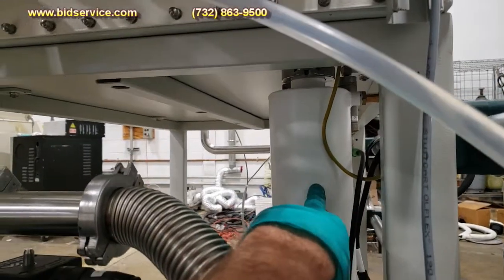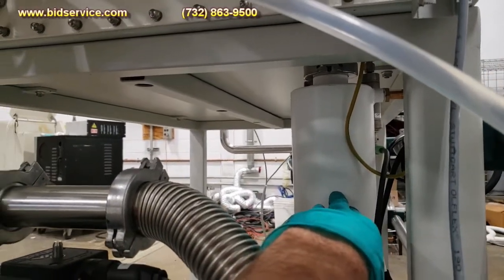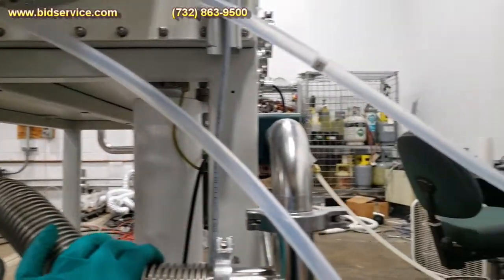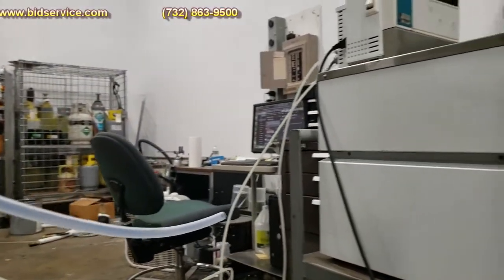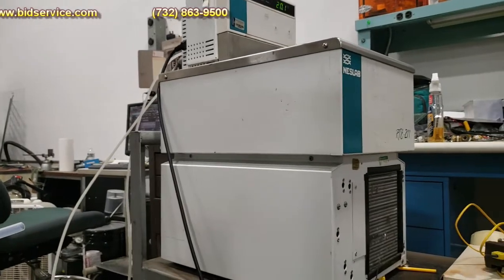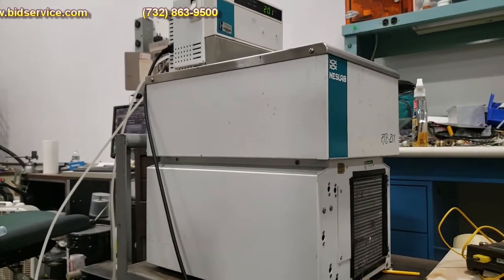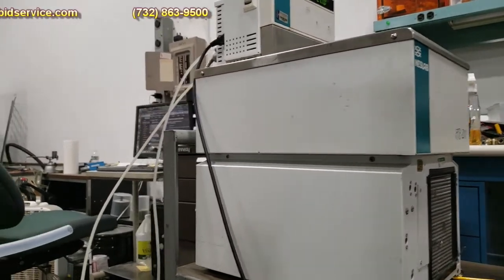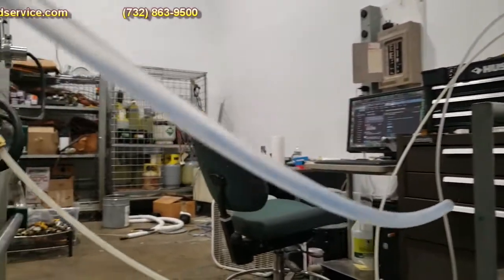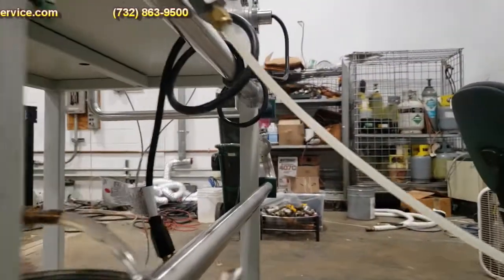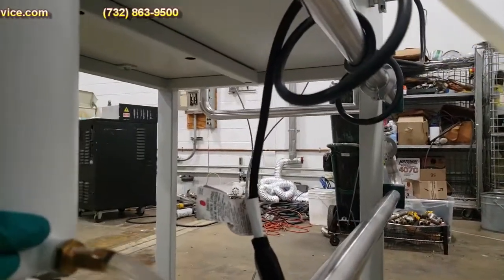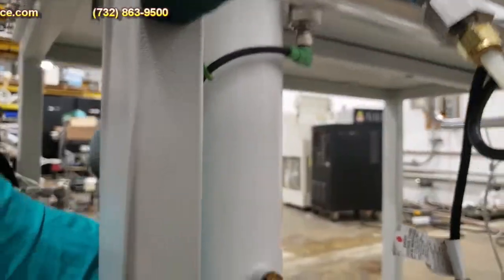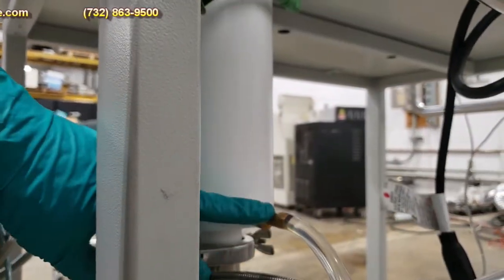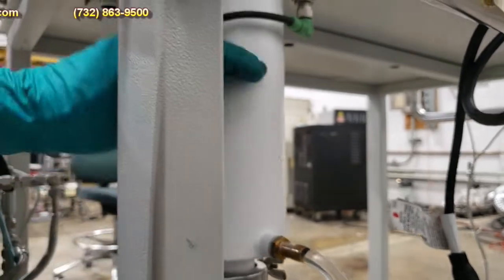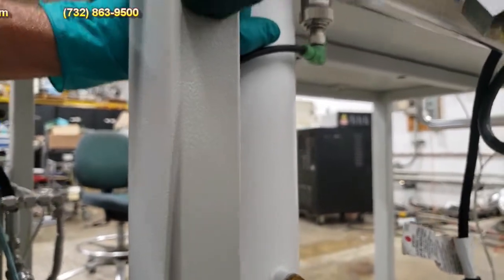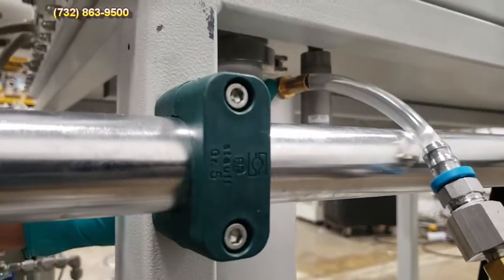The heat's going to be taken off using this heat exchanger here, and we have a house chiller using a Neslab RTE 211 here, set at 20 degrees Celsius, supplying water to the heat exchanger. Typically, I'll put the cooling line, the inline, to the bottom, and the return back to the chiller up here on the top.